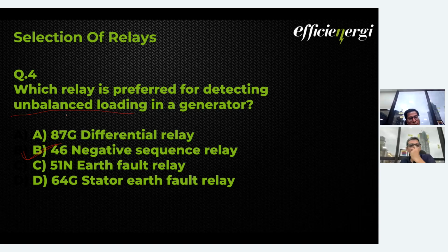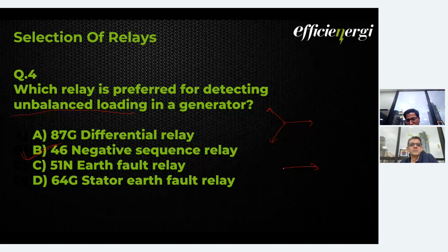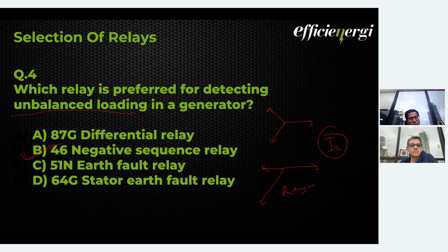Because in balanced conditions everything is going perfectly, but in unbalanced condition, it's not at all perfect, right? If you resolve these components, you will see negative sequence current is more. So I2 you will find more, and it's very easy to have a 46 installed, and it will measure the negative sequence current. Maybe you can set it to 10 to 20%, and time delayed as well.